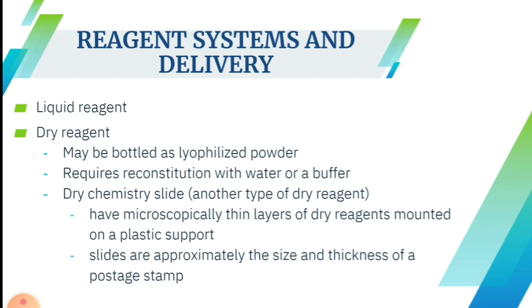Many test procedures use sensitive, short-lived working reagents, so contemporary analyzers use a variety of techniques to preserve them. One technique is to keep all reagents refrigerated until the moment of need and then quickly pre-incubate them to reaction temperature, or store them in a refrigerated compartment on the analyzer that feeds directly to the dispensing area.